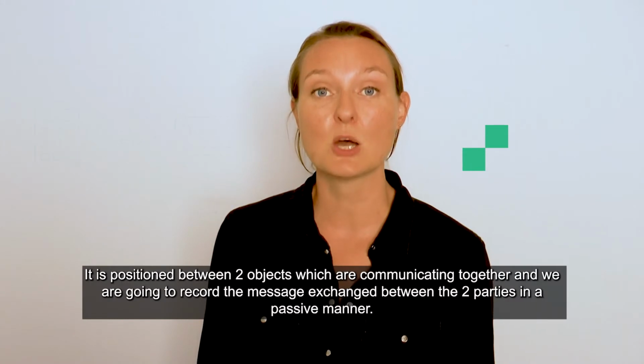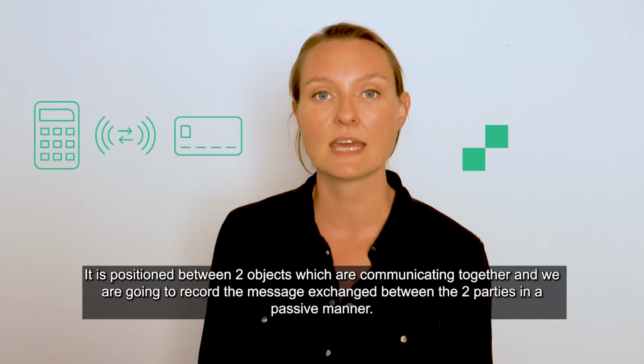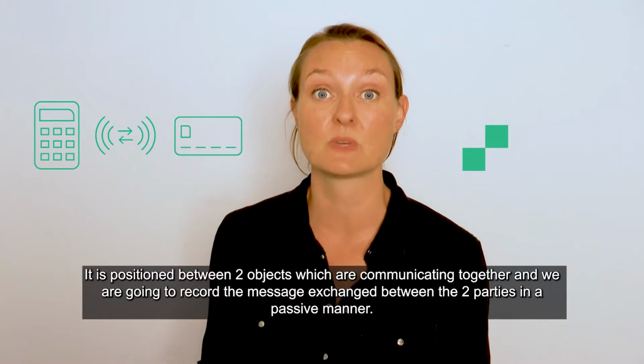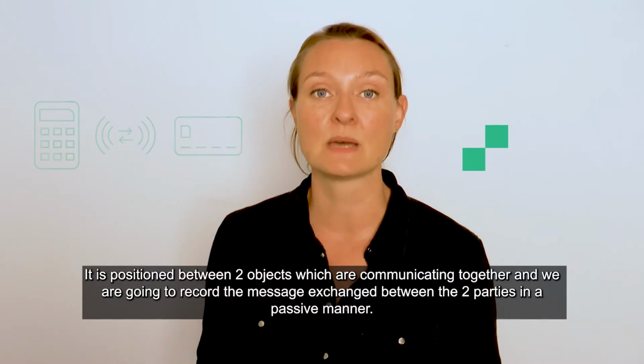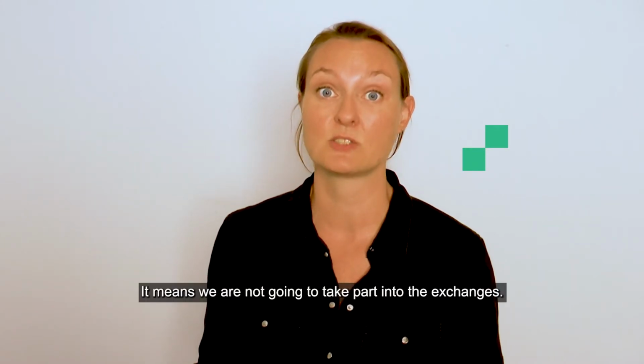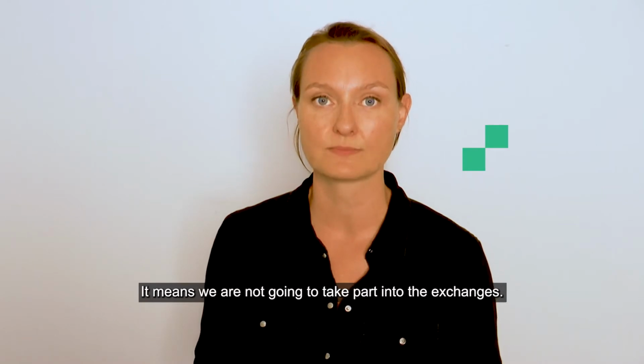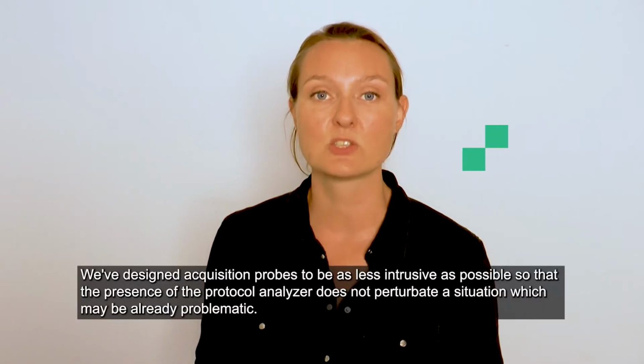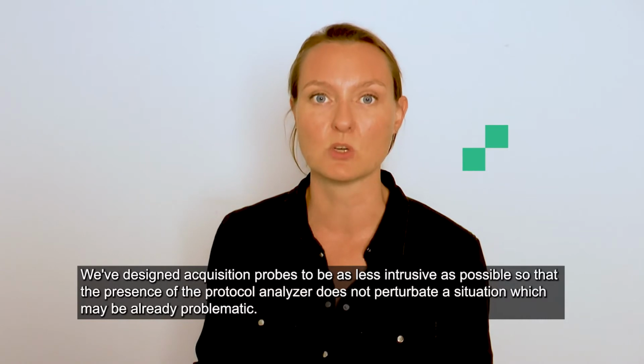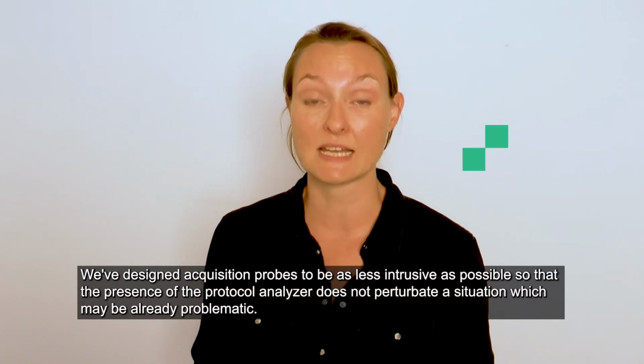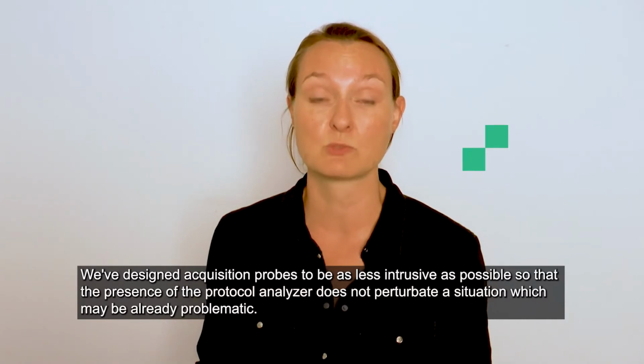How does a protocol analyzer work? This tool is positioned between two objects which are communicating together, and we are going to record the exchange between the two parties in a passive manner. It means that we are not going to take part in the exchanges. We've designed the acquisition probe to be as less intrusive as possible, so that the protocol analyzer does not perturb a situation which may already be problematic.